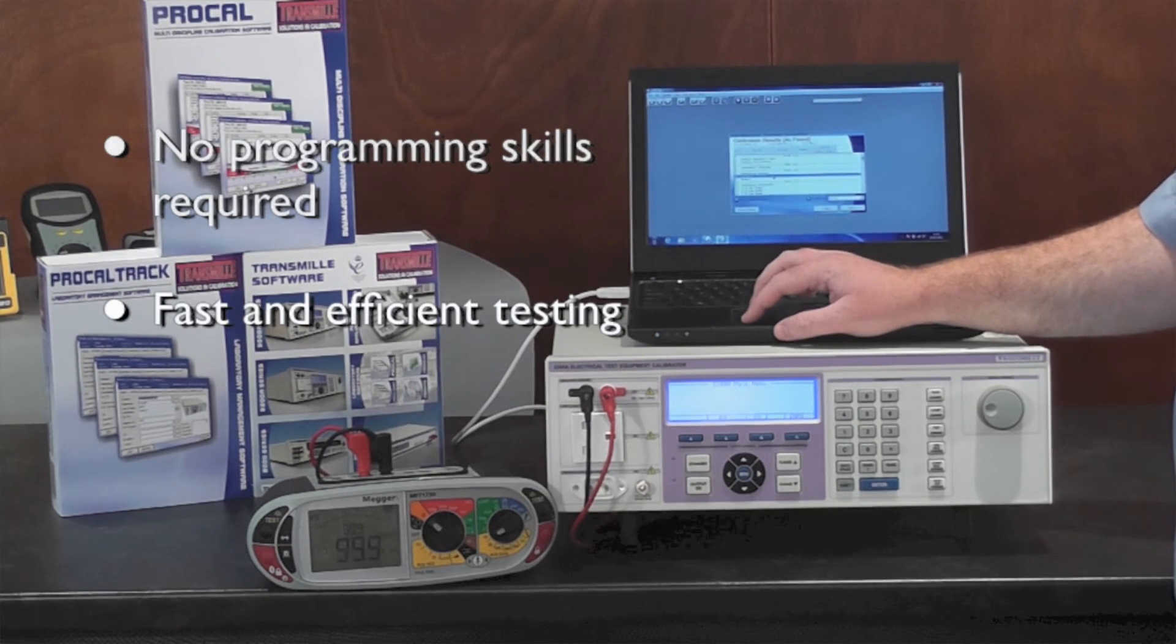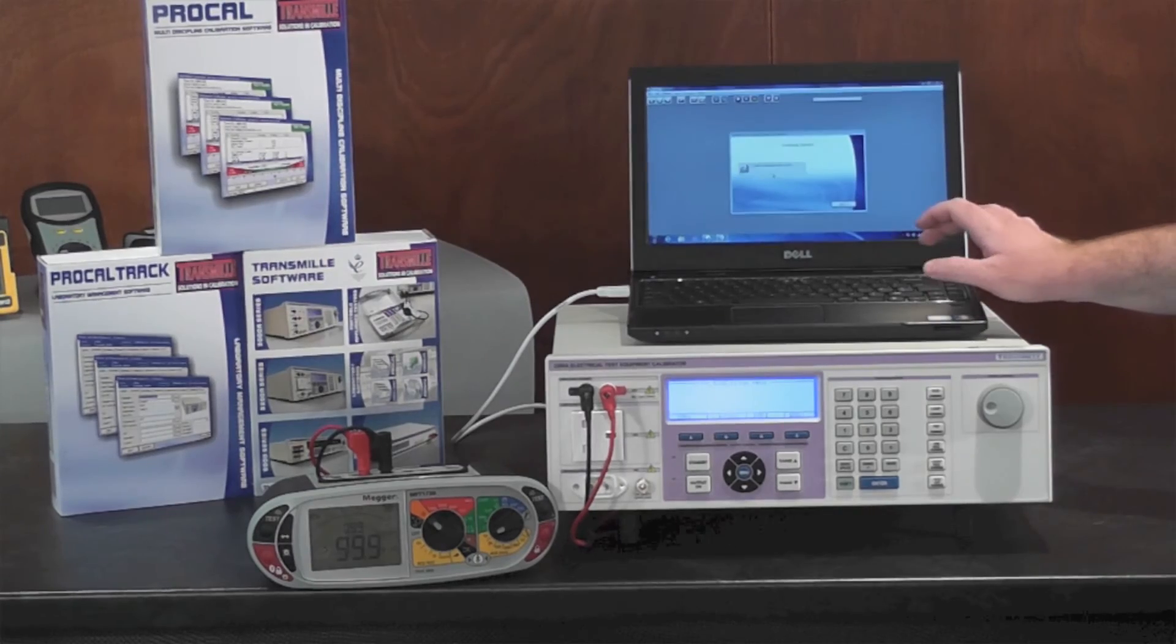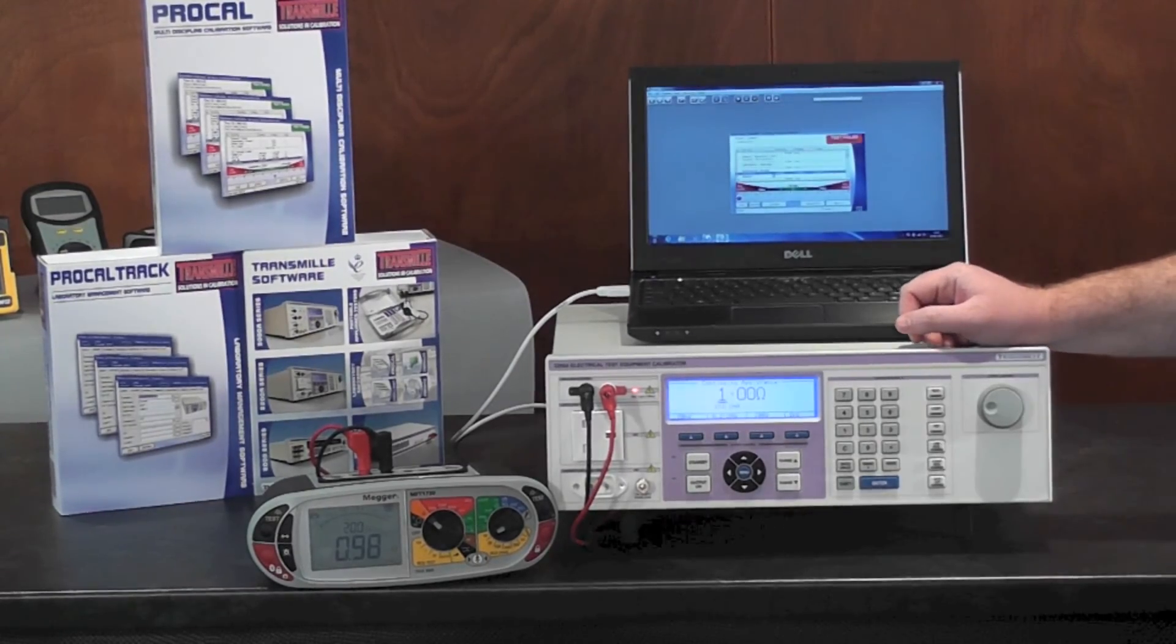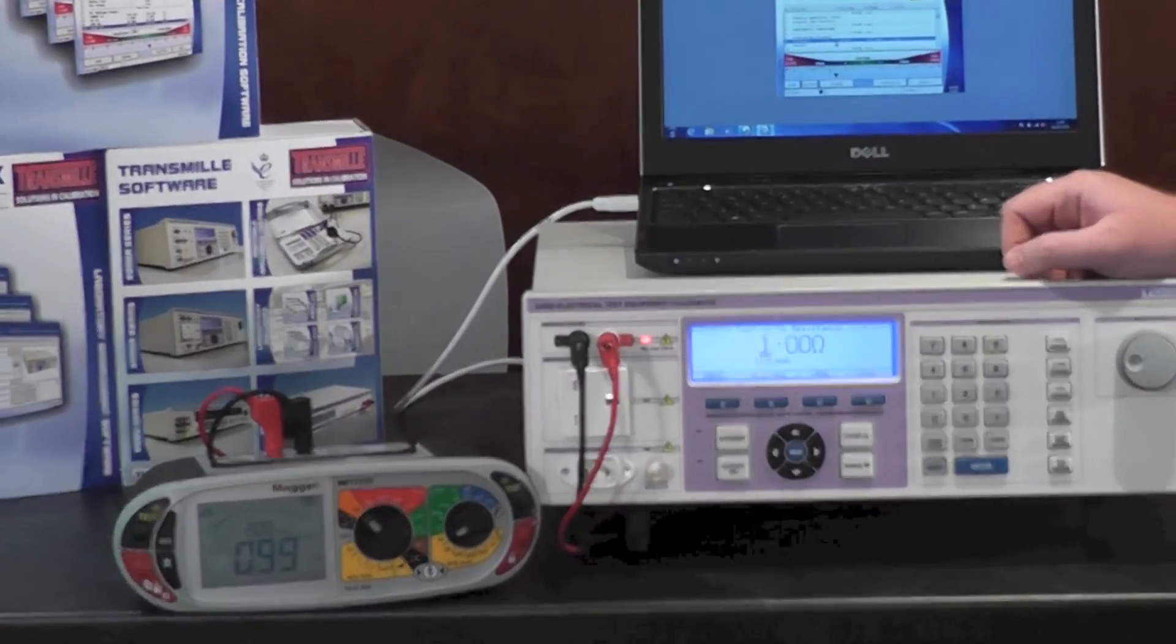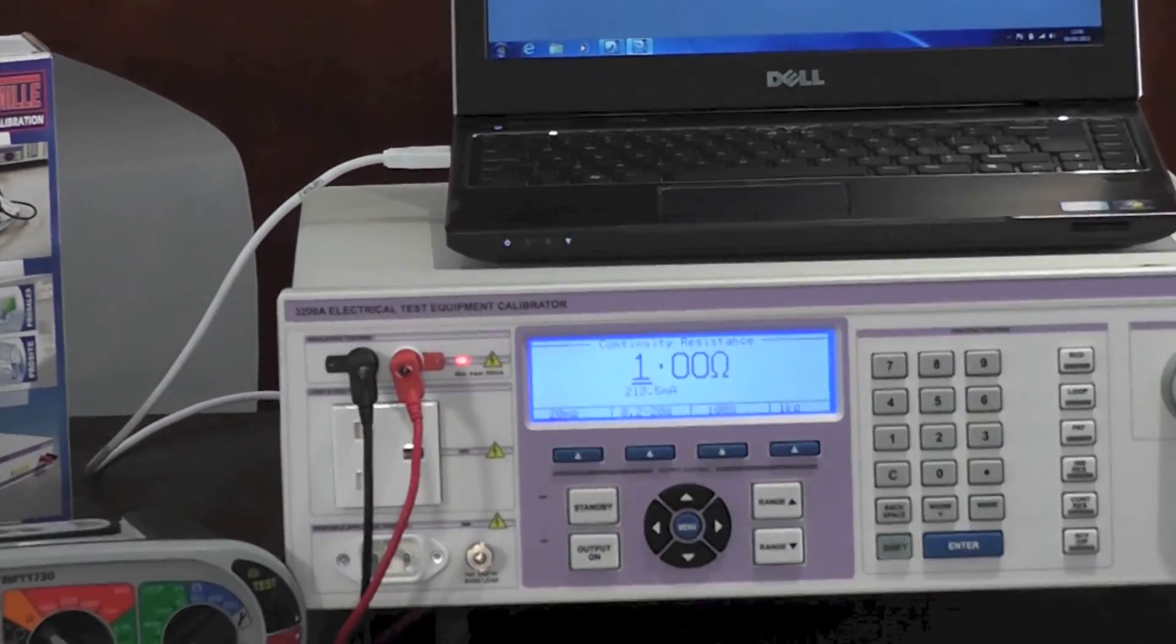For example, measuring continuity current from this tester. I press next. It automatically sets the 3200 to the correct range and begins to read back the continuity current measured from the tester.